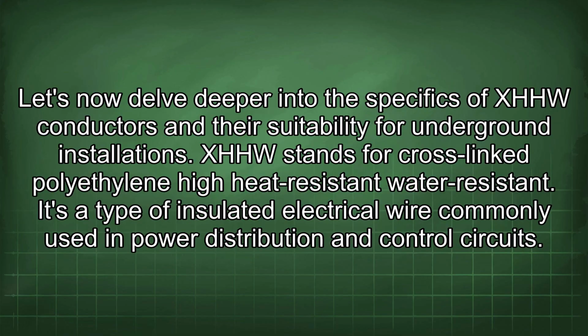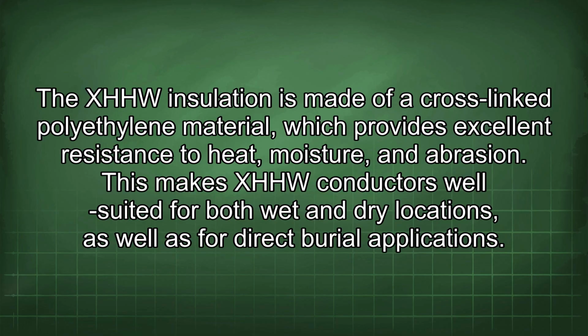Let's now delve deeper into the specifics of XHHW conductors and their suitability for underground installations. XHHW stands for cross-linked polyethylene high heat resistant, water resistant. It's a type of insulated electrical wire commonly used in power distribution and control circuits. The XHHW insulation is made of a cross-linked polyethylene material, which provides excellent resistance to heat, moisture, and abrasion. This makes XHHW conductors well suited for both wet and dry locations, as well as for direct burial applications.